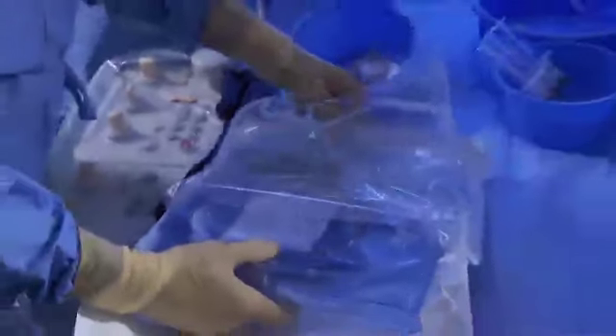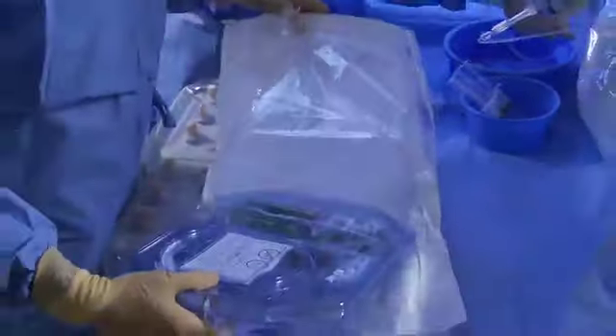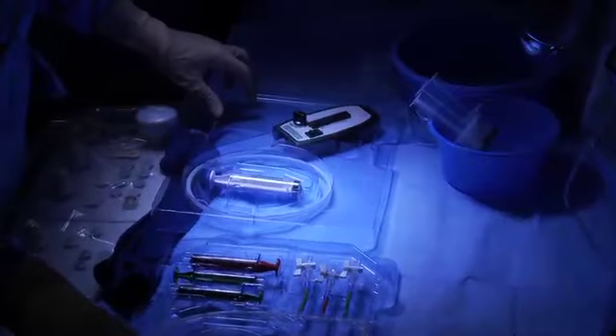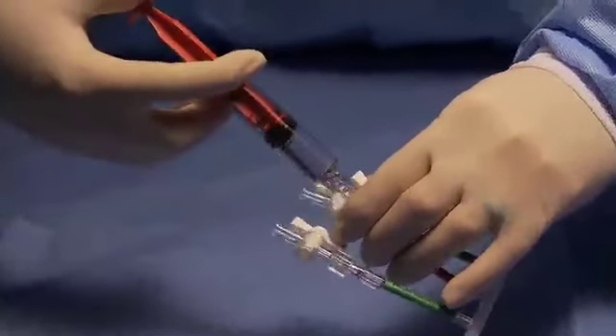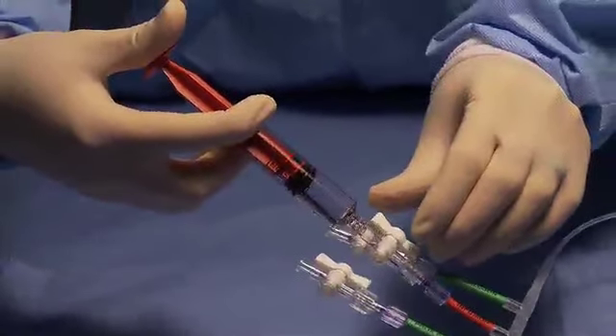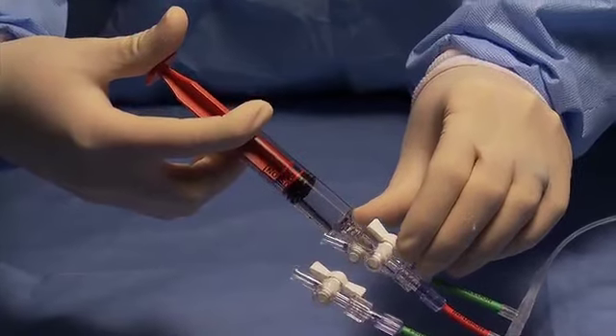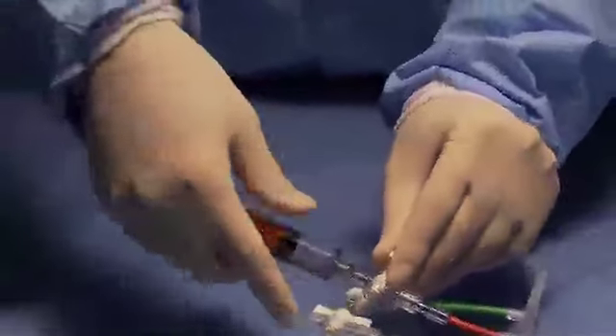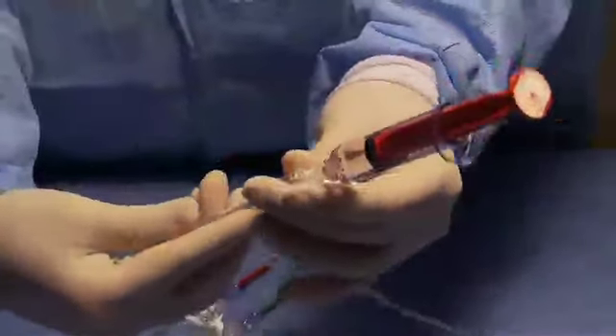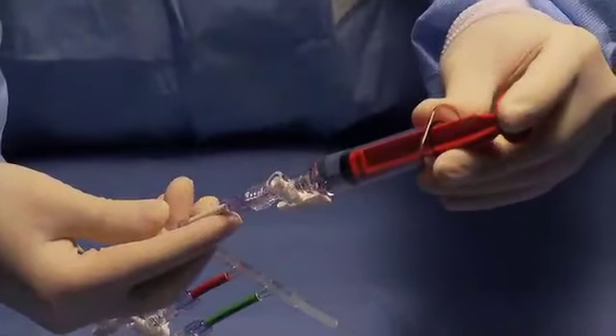Using sterile technique, open and pass the Trellis system onto the sterile field. Remove the catheter, ancillary equipment, and ODU from the packaging. Next, flush the infusion and aspiration lumen with heparinized saline. When flushing the aspiration lumen, place thumb over the hole at the end of the manifold while injecting. After flushing the ports, close each stopcock.